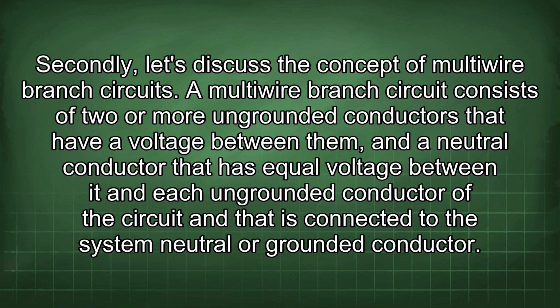Secondly, let's discuss the concept of multi-wire branch circuits. A multi-wire branch circuit consists of two or more ungrounded conductors that have a voltage between them, and a neutral conductor that has equal voltage between it and each ungrounded conductor of the circuit, and that is connected to the system neutral or grounded conductor.